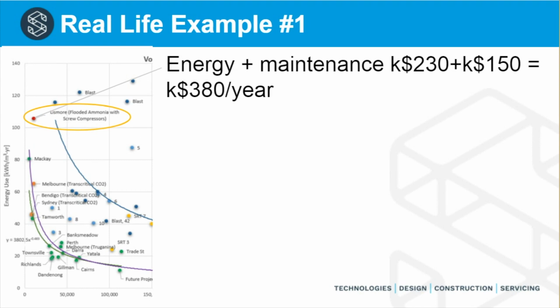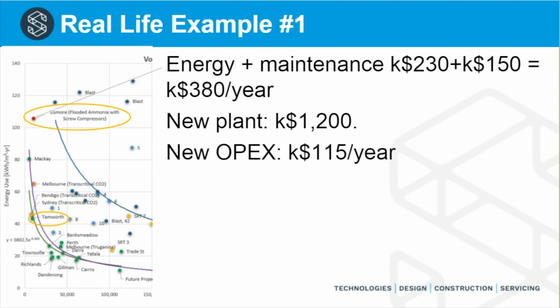This is actually a replacement. You've seen this graph before in the beginning. This is a single stage economized screw compressor plant, which cost nearly $400,000 a year to run. You can see how the figures are made up there. A replacement plant, which is a centralized low charge ammonia plant, will cost $1.2 million. And that plant has got annual operating cost of $115,000 a year. We know this because this client already has a plant like that.